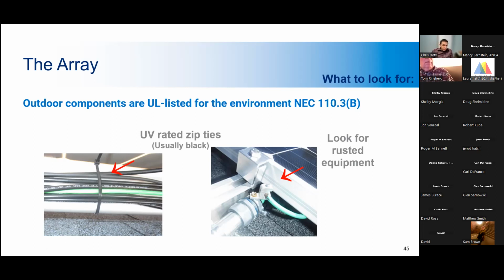Black zip ties are typically UV rated. The white ones, I'm not sure. Sorry about that. The white ones will degrade after not very long, actually, and they'll fail when under sunlight for long periods. I've seen white zip ties degrade in less than a year. So you want to make sure that you have the UV rated zip ties.